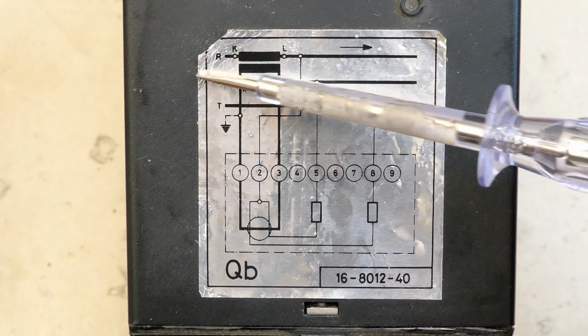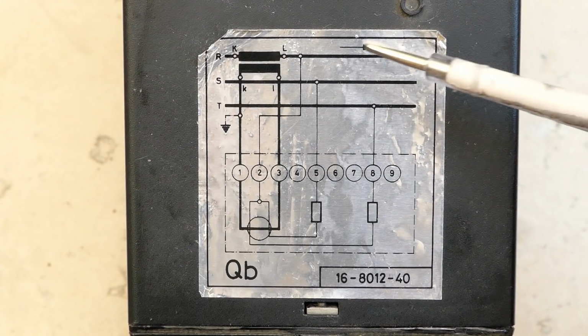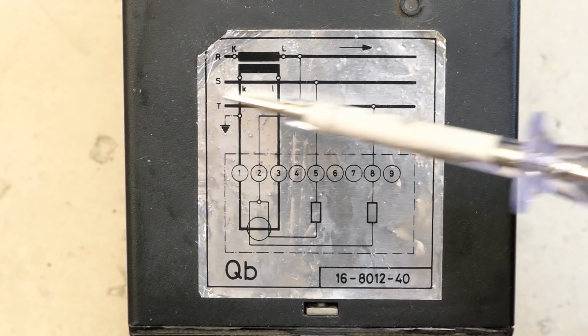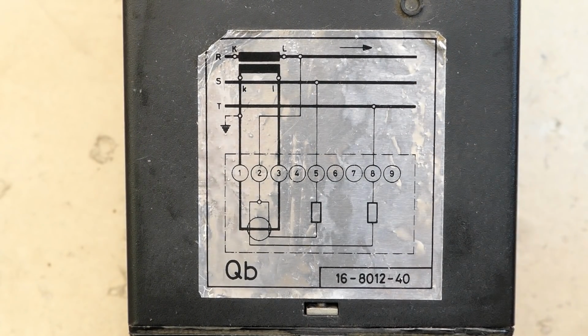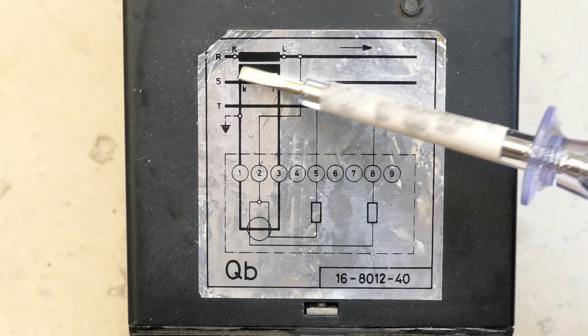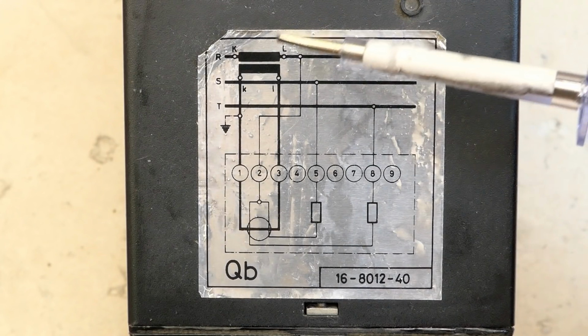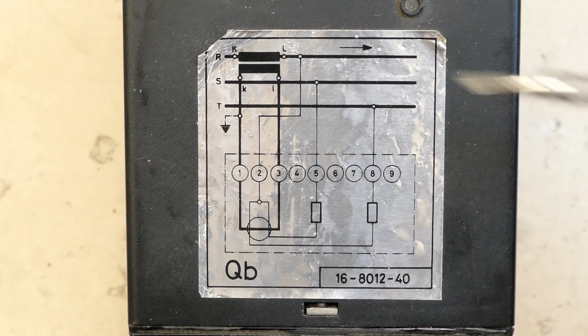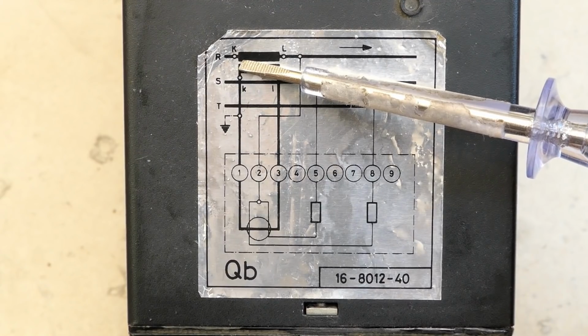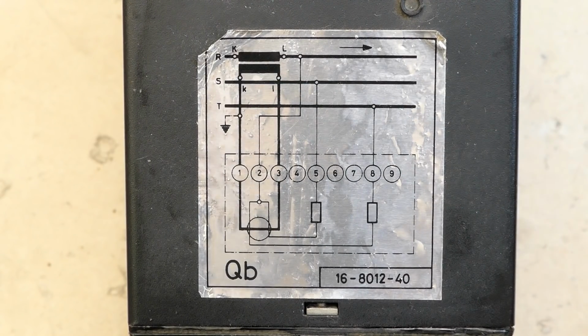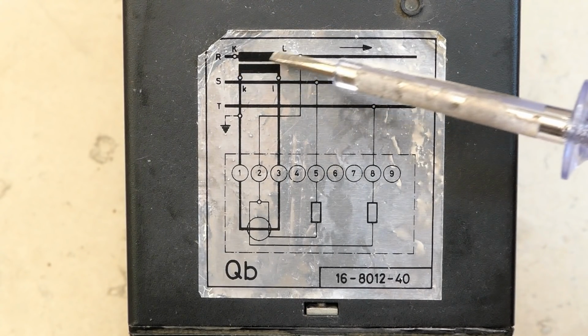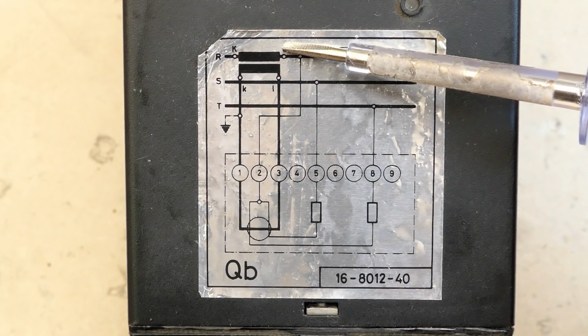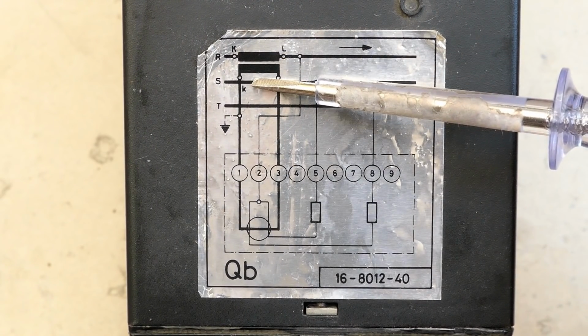These 3 thick lines are the phases, and this arrow indicates that here is the supply and here is the load, and in this case it's sensing the current using a current transformer, which basically steps down the current.